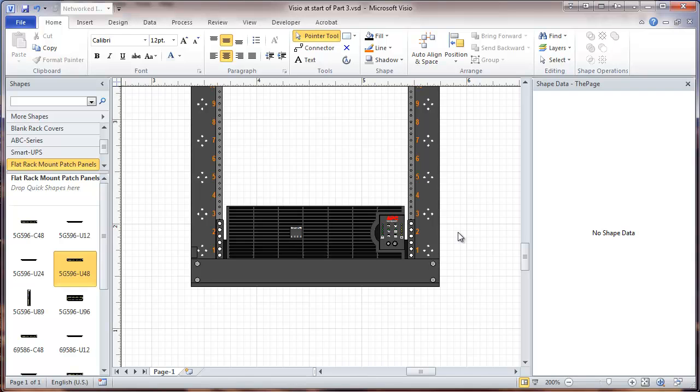The next thing we're going to do here is set up some rack ID. I recommend using standard kinds of arrangements for infrastructure identification. It might be a two-letter code for a building, followed by a floor number, a letter for a series of data closets on that floor, and then a letter or number for each rack within the data closet.